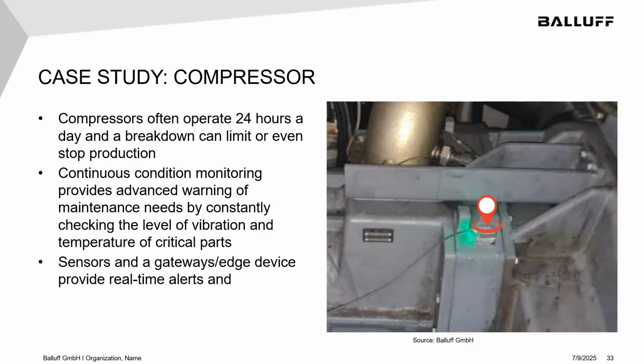This is on a compressor system monitoring for vibration. In this case, the compressor runs 24/7, and they need to know ahead of time if it's going to fail so that they can take it offline during a normal downtime and address the compressor problems, whether it's on a bearing or on the compressor motor, and shut that down and do the maintenance proactively before they have a catastrophic failure.